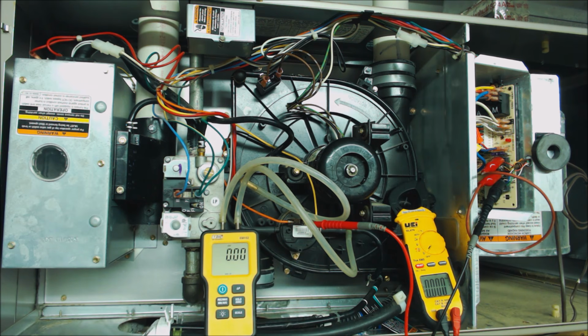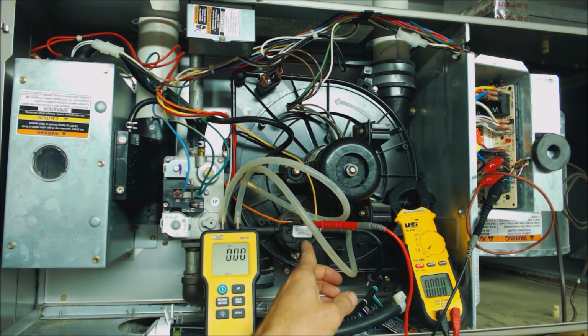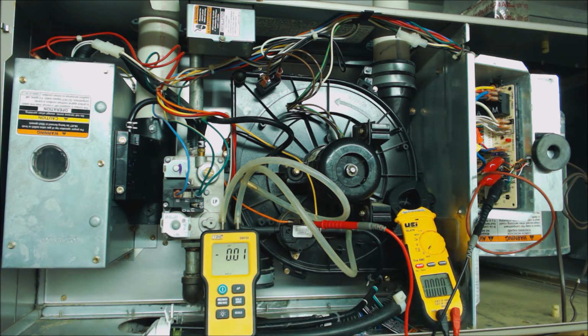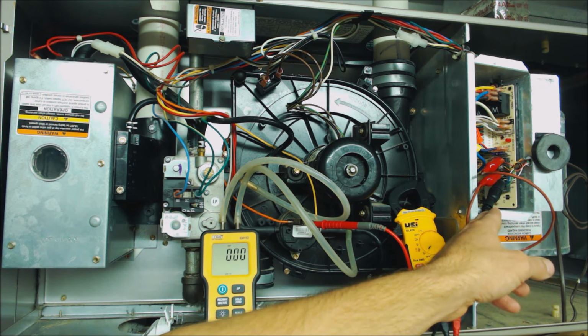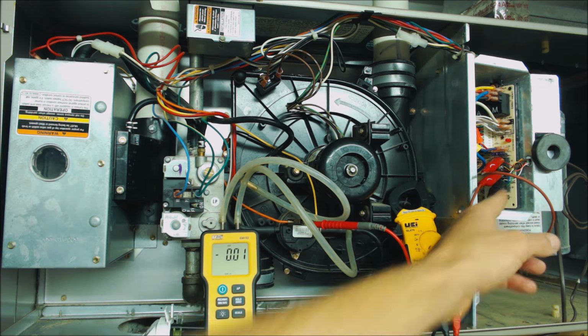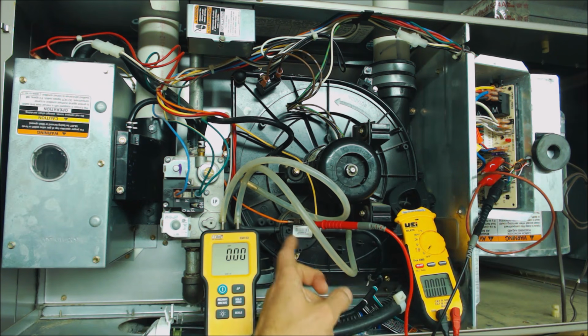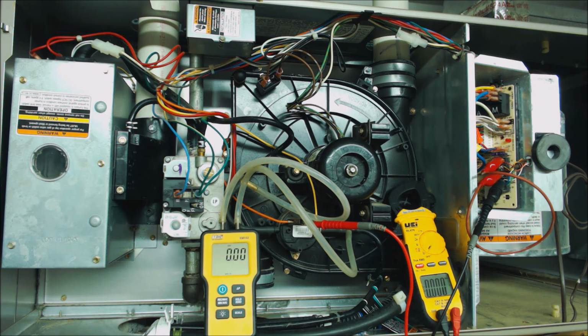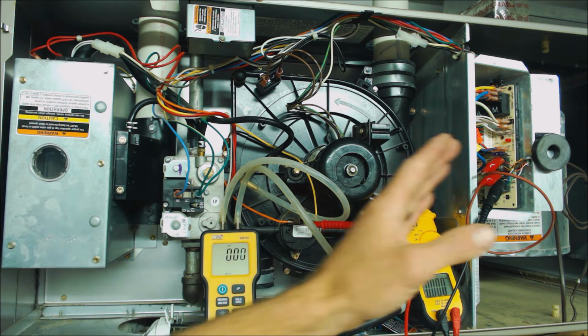And so that's where we're being held up at this point, because we are not getting our pressure differential like we should be. If we do get the correct pressure differential, then we're going to read 24 volts from here to our common terminal. We could also have, instead of this multimeter lead on the common, just put that on the ground, and that would help us as well. We'd be able to still read the 24 volts. Now let's go ahead and turn this on so you know.